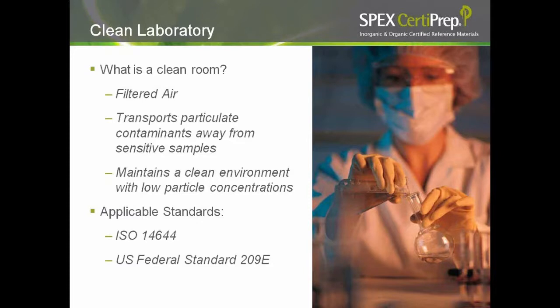What is a clean room or clean lab? It is a room with a gentle shower of highly filtered air for the purpose of transporting airborne particulate contaminants away from sensitive samples and maintaining a clean environment with low particle concentrations. Environment pollutants to consider include dust, airborne microbes, aerosol particles, and chemical vapors. Applicable standards are ISO 14644 and U.S. Federal Standard 209E. A typical clean room has a controlled level of contamination specified by number of particles per cubic foot or cubic meter for a specified particle size.